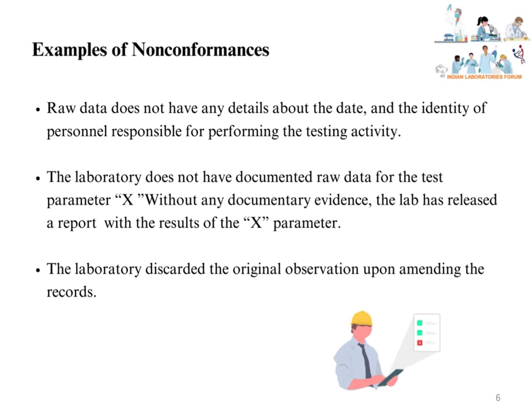Examples of non-conformances as per Clause 7.5: Raw data does not have any details about the date and identity of personnel responsible for performing the testing activity. The laboratory does not have documented raw data for test parameter X without any documentary evidence, yet the lab has released a report with the results of the X parameter. The laboratory discarded the original observation upon amending the records.